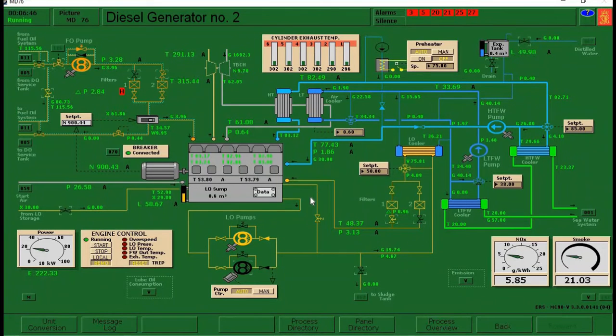Okay. Our diesel generator 2. Our valves here from our DO service tanks are open. We have power generated here. Our discharge valve is closed. Filter open right here. Our LO pump here is running. Okay. And we have a normal level of lube oil in our sump right here.